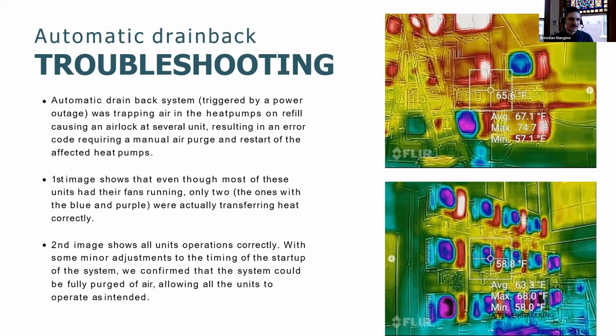Power cuts off, the system will completely purge of water in like 1 to 2 minutes. Way more than enough time to get the water out of the lines before they could get a chance to freeze. The issue was that when they would refill, some air would still get stuck in the lines, even though we did have the automatic air vent. It could cause an airlock at some of the pumps, and they just would go off on high pressure.